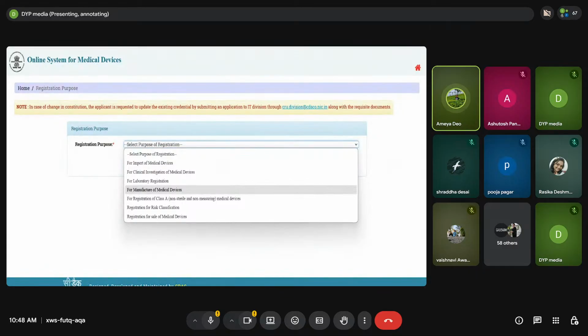When you want to register, there are several purposes for the registration, like if you want to import a medical device, or do a clinical investigation of a medical device. If your device is only for laboratory use, that is in vitro use, you can also do that. Then manufacturing of medical devices for registration of class A, that is non-sterile, non-measuring medical devices. Then registration for risk classification. This is important, because sometimes even with the expertise of regulatory professionals, you can't identify the risk type or class of your device. In this case CDSCO helps you. You just need to register via this, that is, registration for risk classification.